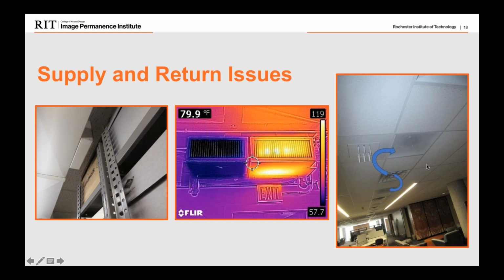What happens in a scenario like this, the air will be exhausted from the supply vent, and almost immediately half of that air will be drawn right back into a return vent. A lot of that air isn't making it into the collection space, conditioning the space at all, and we refer to that as short circuiting, because a lot of the air is coming right out and just going right back to the unit. And the third image, the middle image, is a little harder to identify, but we used an infrared camera walking through when we evaluate a space, and we were able to identify both ducts coming from one air handling unit where one was heating and one was cooling. In a scenario like this, the system is fighting itself, trying to create a condition to compensate for the lack of heating on the other vent.